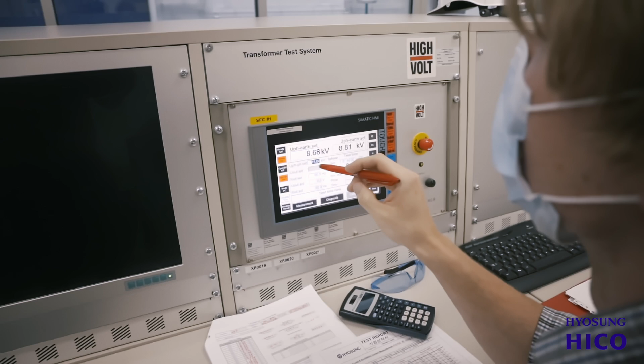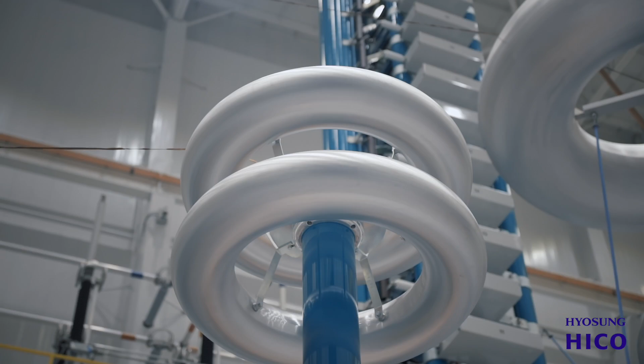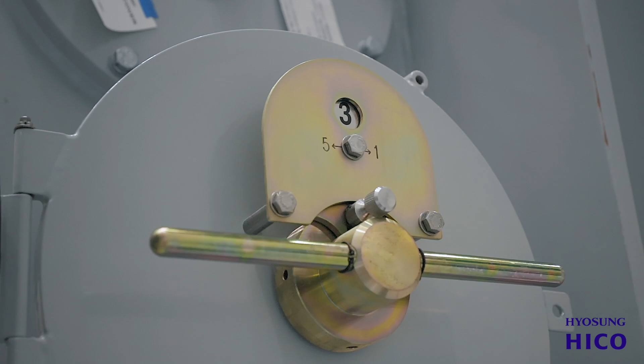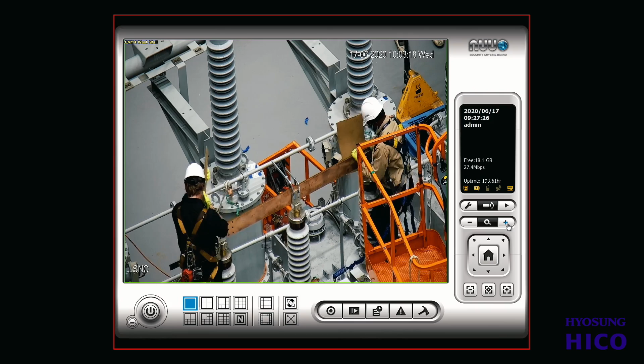My name is John Adam Dower, and I am the test lab engineer for Hyosung HICO. We just run the routine tests and the tests that international specifications and the customer specifications decide that they want run. Special tests that customers may require. We might have to do leakage reactance or step function tests that haven't been done on any unit. So we have to figure out how to do those very specific tests. Even those, once you do it one time, for the next unit it's going to be the exact same. So in general, the testing process is pretty straightforward and easy.